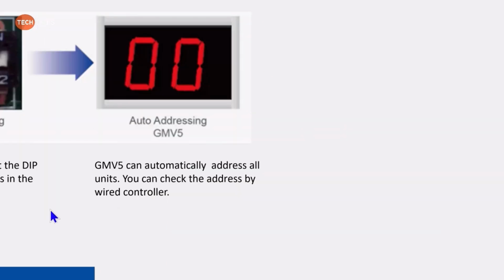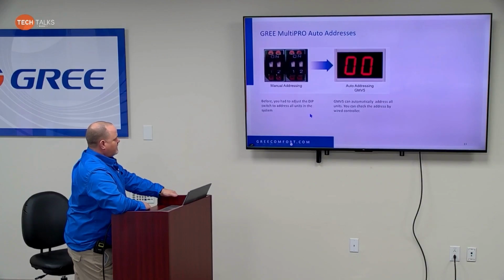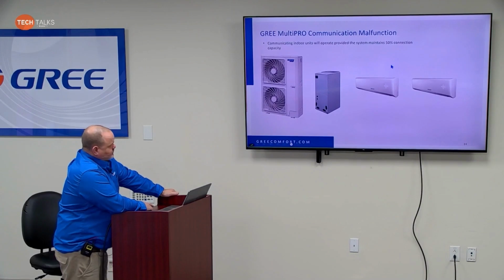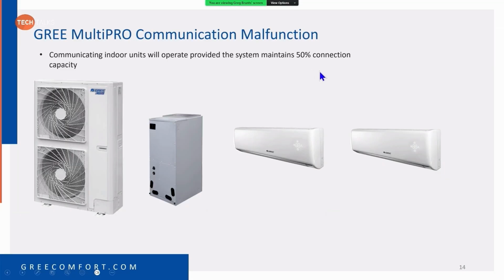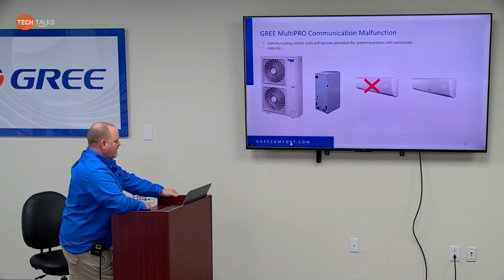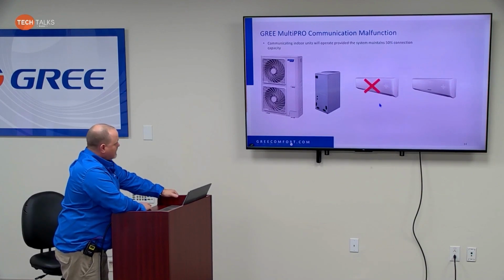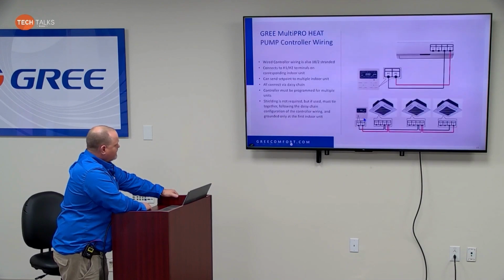With MultiPRO, they are self-addressing, so you don't have to set dip switches or anything like that. It will automatically adjust. You have to maintain a 50% connection capacity ratio, so I always make sure I stress that. Like if I lose one indoor unit, let's say this is a 4-ton unit, and this is a 2-ton air handler, and you've got a 9K and a 7K, I could actually lose both of these, because this 2-ton is still going to be 50% of the outdoor unit, and the system will still run. But if I've got a 9K and a 7K here and I lose the 2-ton, then the system can't run, because now I'm below 50% connected capacity. Okay, so that's good information to have as well. So it will continue to heat and cool.